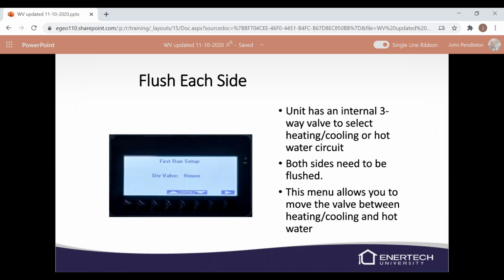And if it's in-house and you need it to go to the hot water mode, then you're going to have to scroll down until you get to this little house word, and it'll be kind of darker. You can press enter and you can change it, and that valve will shift for you. So that way you can make sure that you've got the load and your hot water circuit flushed out.